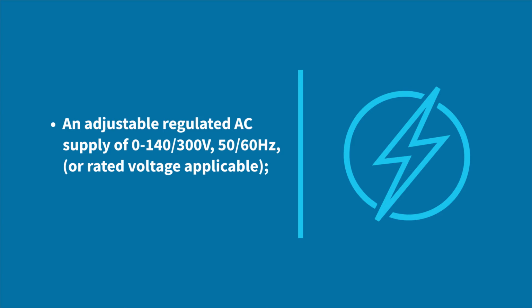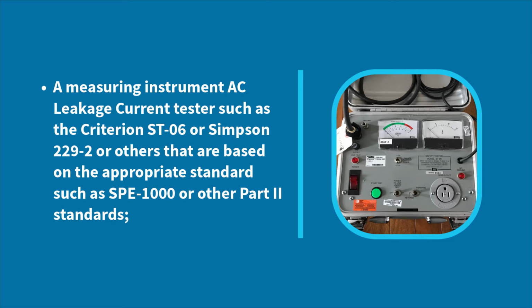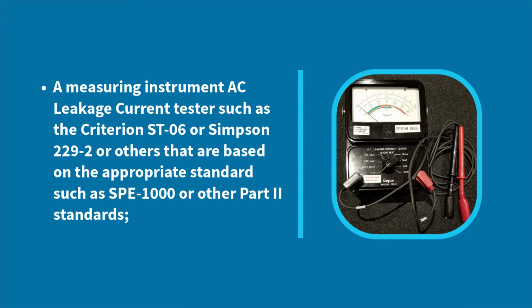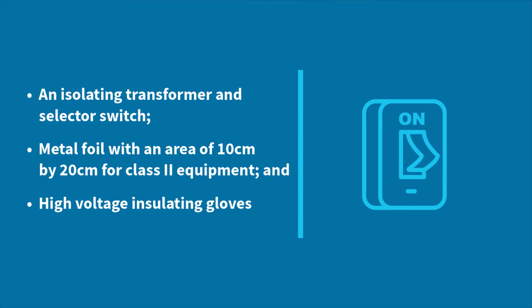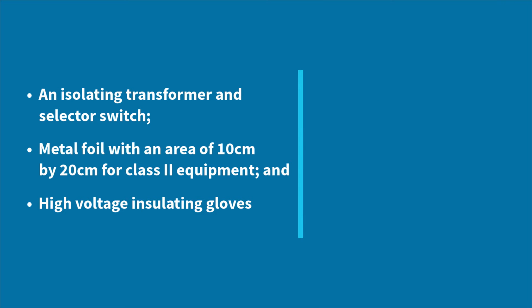Test apparatus. For this test, you will need an adjustable regulated AC supply of 0 to 140 or 300 volts, 50 or 60 Hz, or rated voltage applicable. A measuring instrument AC leakage current tester such as the Criterion ST06 or Simpson 229-2 or others that are based on the appropriate standards such as SPE 1000 or other Part 2 standards. An isolating transformer and selector switch, metal foil with an area of 10 cm by 20 cm for Class 2 equipment, and high voltage insulating gloves.